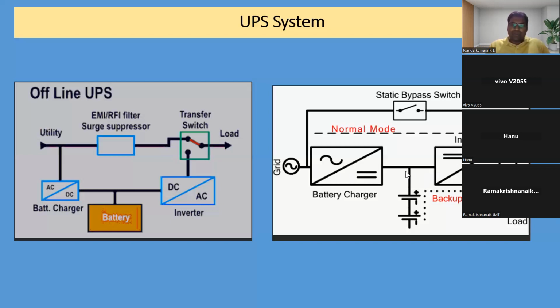So in case the grid power fails, the battery voltage will always be available. Charging and discharging happen at any given time, and it will be available on the inverter side within 300 milliseconds. Within 300 milliseconds, the battery voltage will give continuous power, so there will not be any interruption. Anything above 800 milliseconds, if an interruption happens, then it will disconnect the power. Anything less than 800 milliseconds, any changeover, will not give an interruption, meaning it will not break the cycle. The sine wave cycle will not get broken. So that is why this UPS system is used.